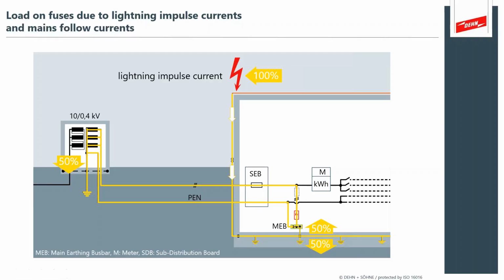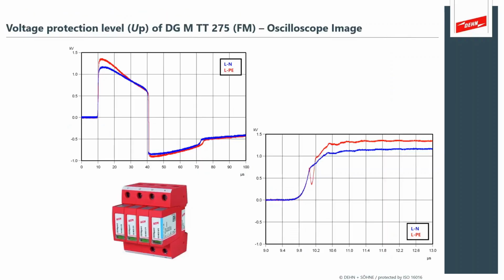So this is how it's described in the standards, that when you get struck, you can expect something to happen, and that's that voltage rising around your system. And then when this surge protection is trying to operate, you can actually have follow currents and things as well, and these are all part of the surge world. But this is essentially the short description of what's being induced into your systems. And this is just a quick photograph of the image off the oscilloscope. This is what you're doing. You're chopping the spike off and allowing the AC power to operate transparently. And you're inducing the surge into the return. Essentially, you're diverting the surge.